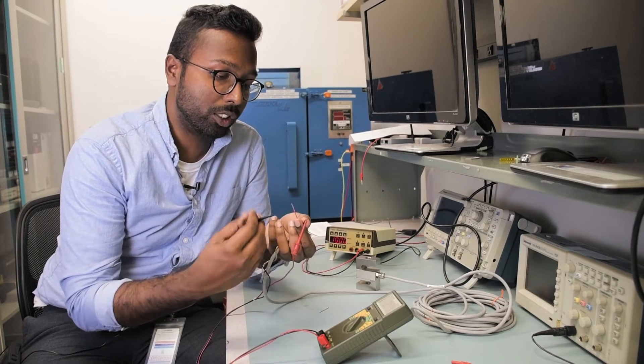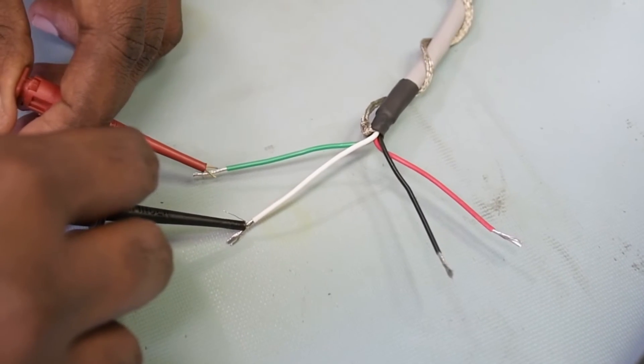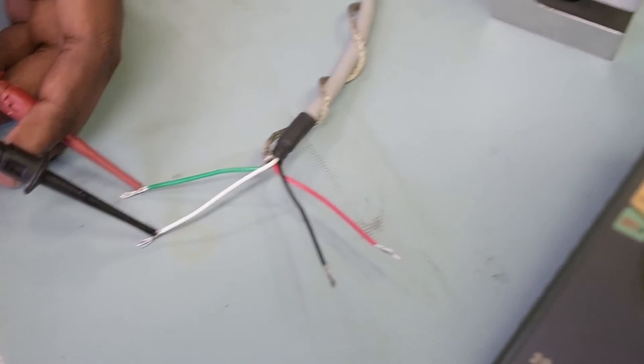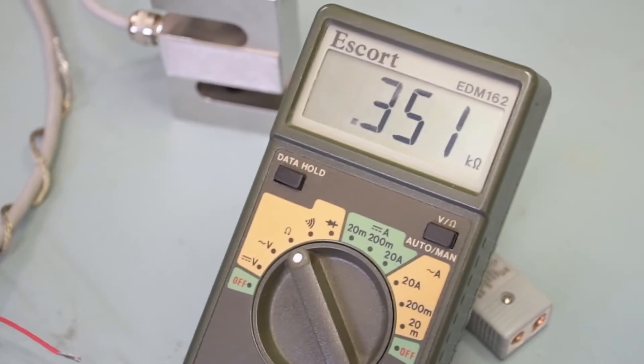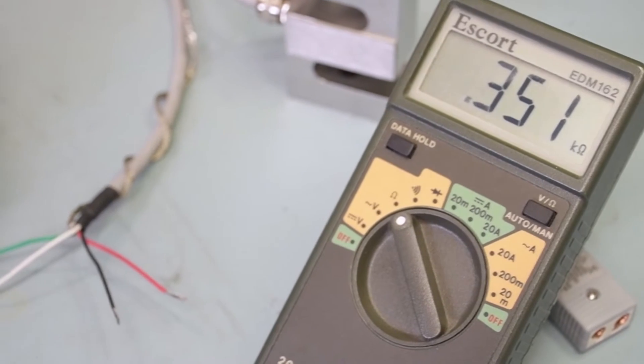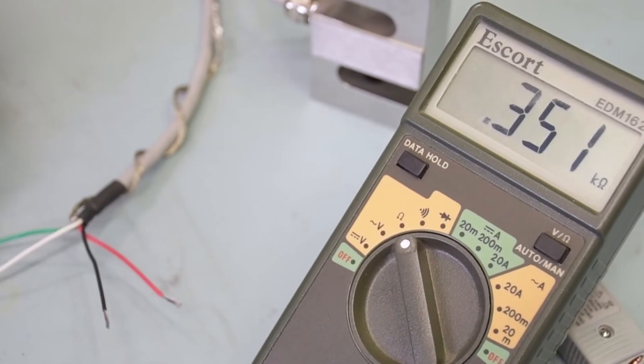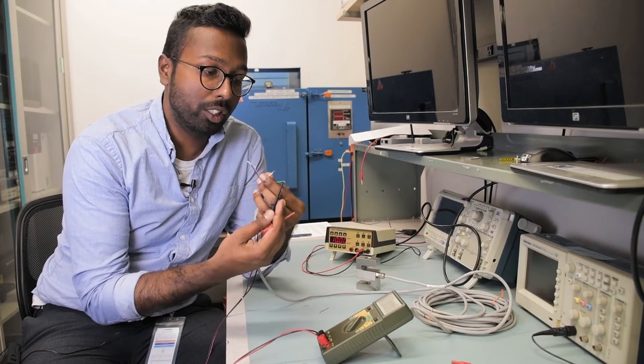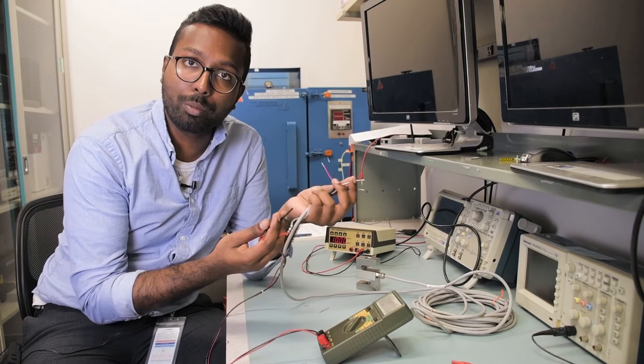Now measure the resistance across your signal leads, which in my case would be across green and white. According to the calibration certificate, it should read 351.70, and I'm reading 351, which is fairly close enough. This indicates a balanced bridge—a balanced 350 ohm full bridge circuit.